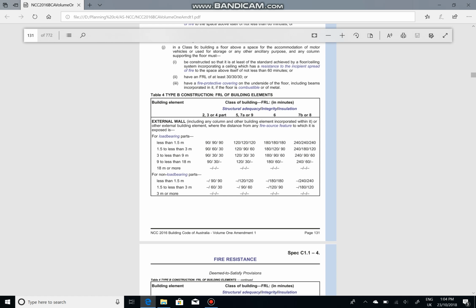Also, these numbers, if you don't know already, you should know, but if you don't, I'll give you a quick rundown of what they are. That first 90 is for structural adequacy, the second 90 is for integrity, and the third 90 is for insulation. All of these are expressed in minutes, so 90 minutes, that's 1.5 hours. So for 1.5 hours, under the conditions of a fire, that wall has to maintain its structural adequacy, i.e. it has to keep holding up any of the loads that it's bearing, it has to maintain its integrity.